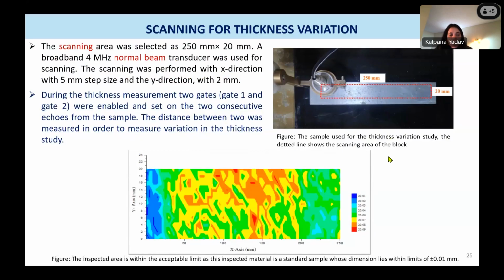I selected that, and if you see here, I was measuring the thickness. And from this C scan system, from the C scan image, you can easily see these different colors in the C scan image showing how much variation there is in your rod. So if you see the blue portion at the start, between 0 to 50 on the x-axis, the thickness on this side is like 20.01 to 20.03 or something, not more than that. You can easily see how much variation there is in the thickness.